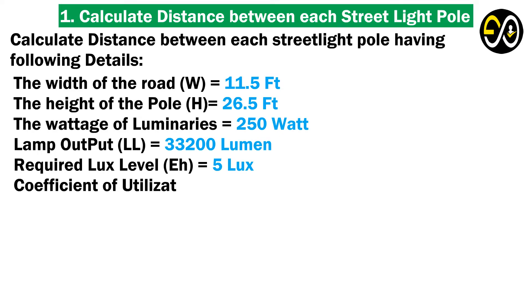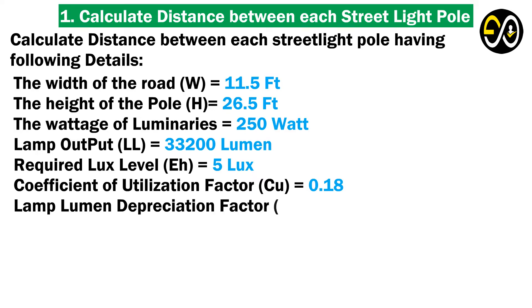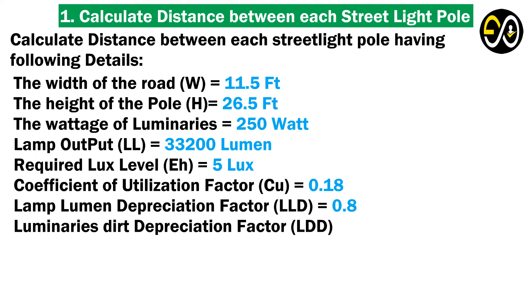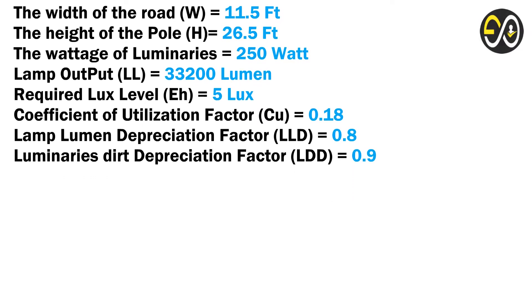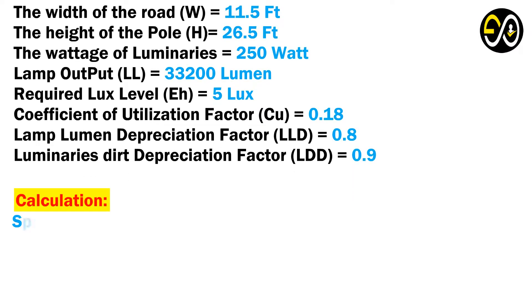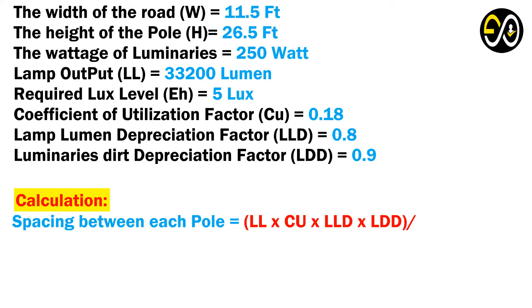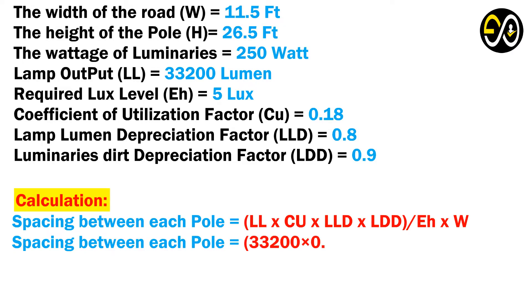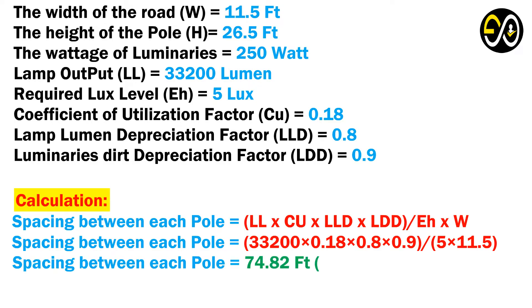Coefficient of utilization factor CU equals 0.18. Lamp lumen depreciation factor LLD equals 0.8. Luminaires dirt depreciation factor LDD equals 0.9. Calculation: Spacing between each pole equals LL times CU times LLD times LDD, over Eh times W. Spacing equals 33,200 times 0.18 times 0.8 times 0.9, over 5 times 11.5, which equals 74.82 feet.